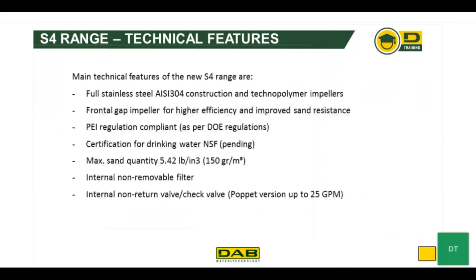The main technical features of the new S4 range: it has a full 304 stainless steel construction with technopolymer impellers. It has a frontal gap impeller for higher efficiency and improved sand resistance. It is regulation compliant, with certification for drinking water from the NSF. It has an expanded sand quantity that can be pushed through the pump without damaging it. It has an internal non-removable filter, and it has an internal non-return or check valve. And up to 25 gallons per minute, that is the poppet version.